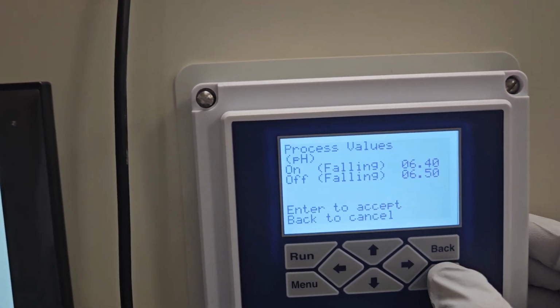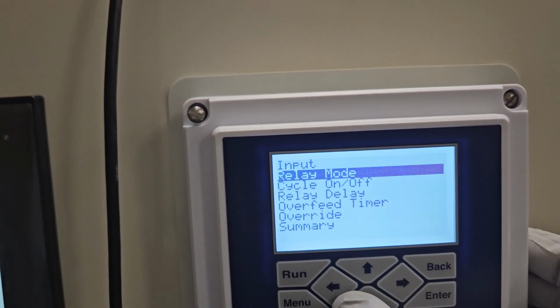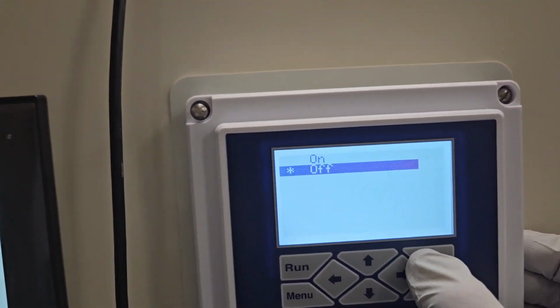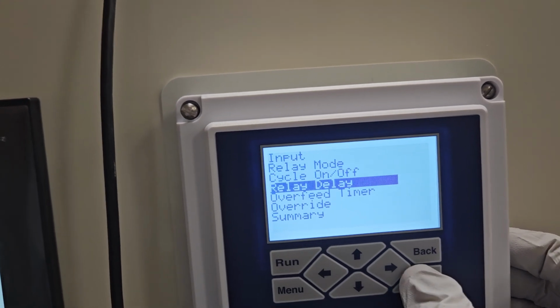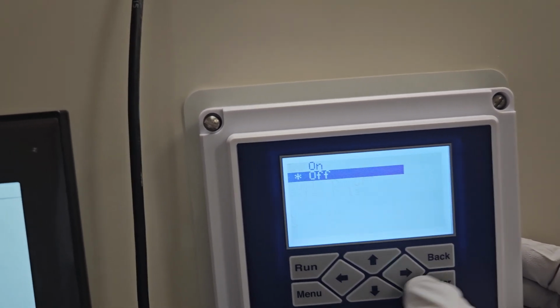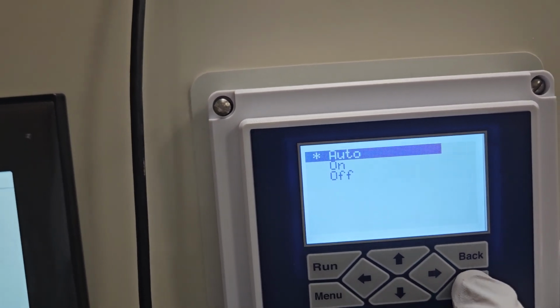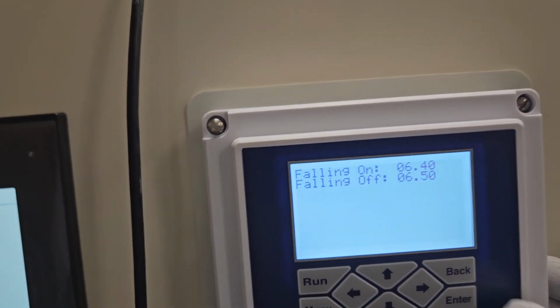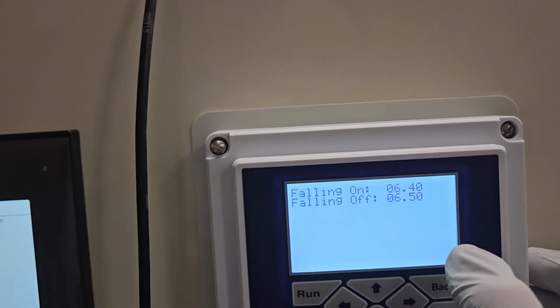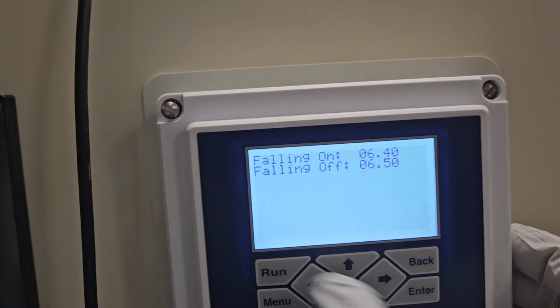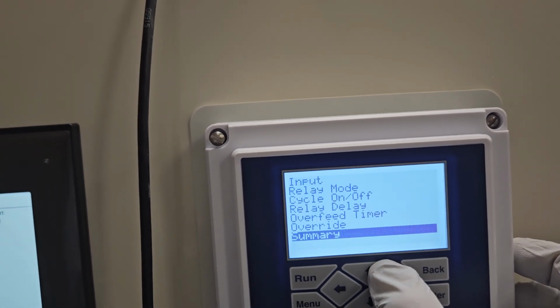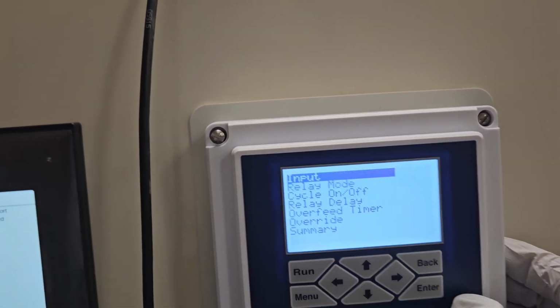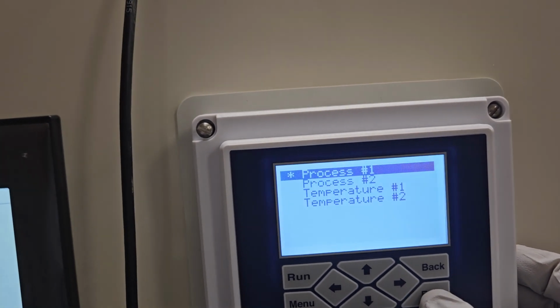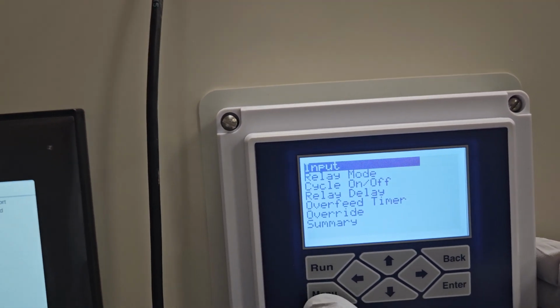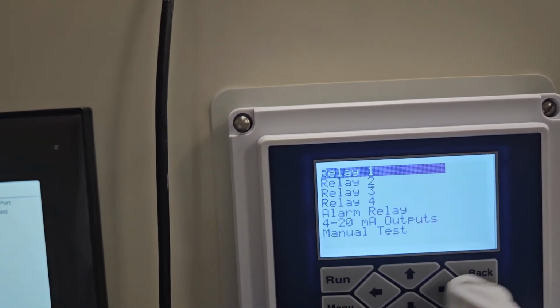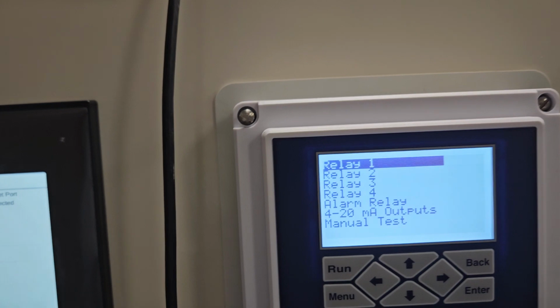So I hit enter to accept, and that's the relay mode. We don't use the cycle on and off, so that's off. Relay delay, we don't use that, it's off. We don't use the overfeed timer, that's off. Override is on auto. So there's the summary. Falling, 6.4, 6.5, okay? Back. So that's the relay mode. Your input is process 1. And back. So that's your relay 1. It's already set up. And that's how we set up.